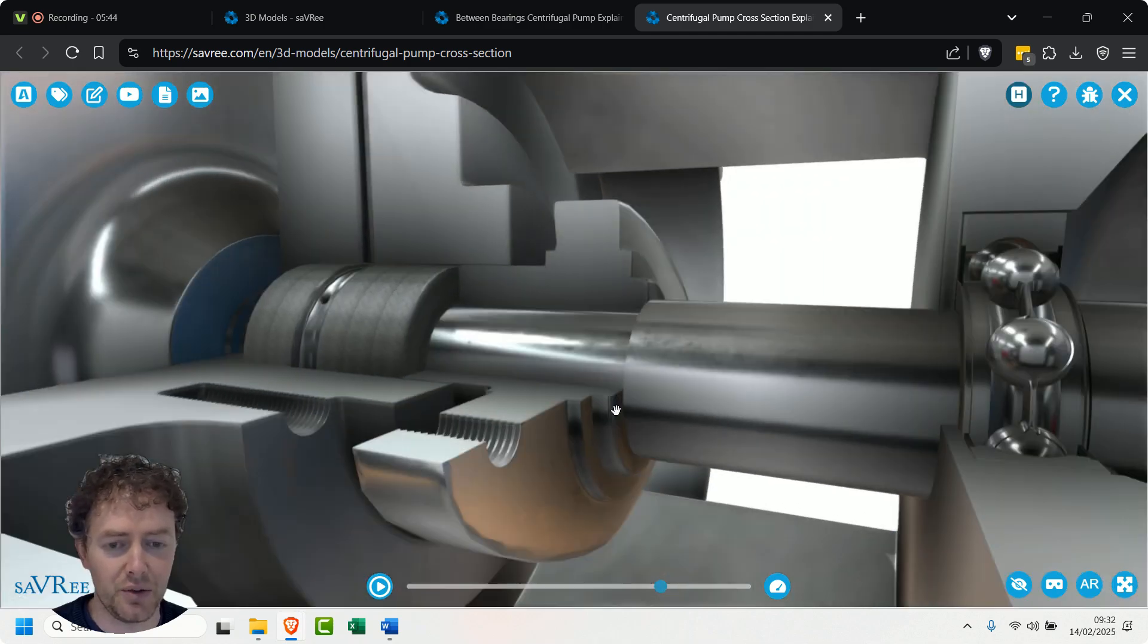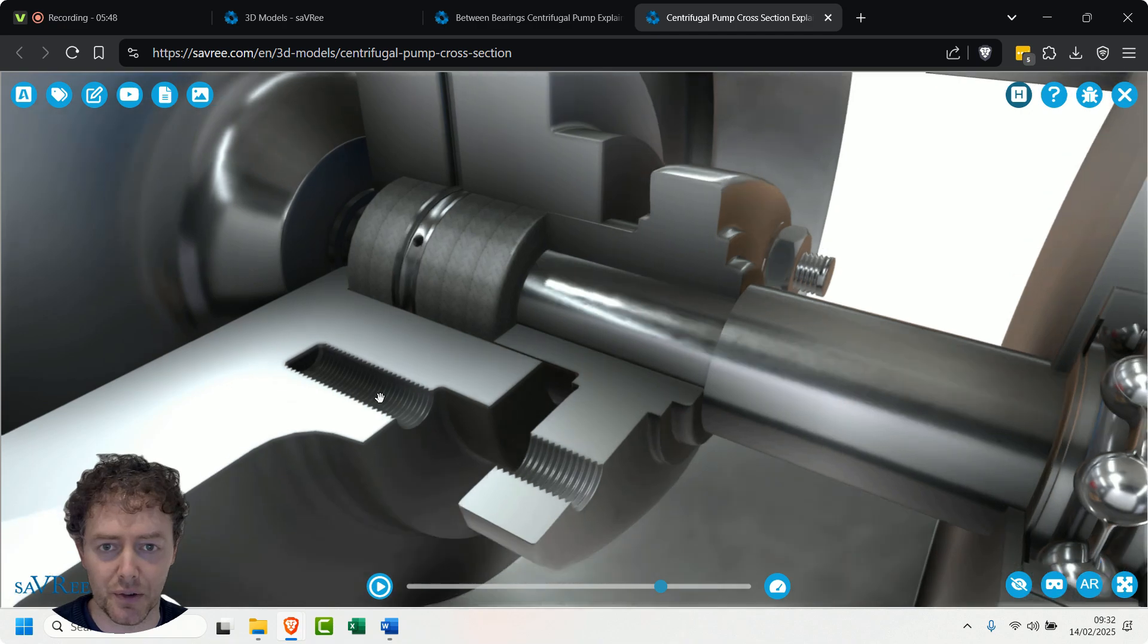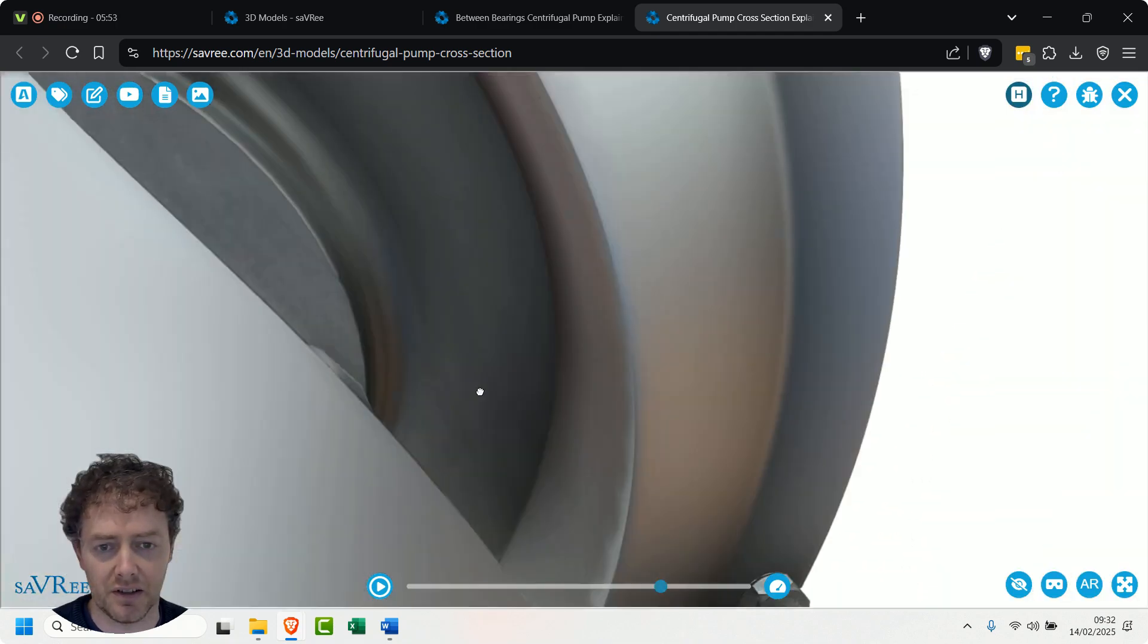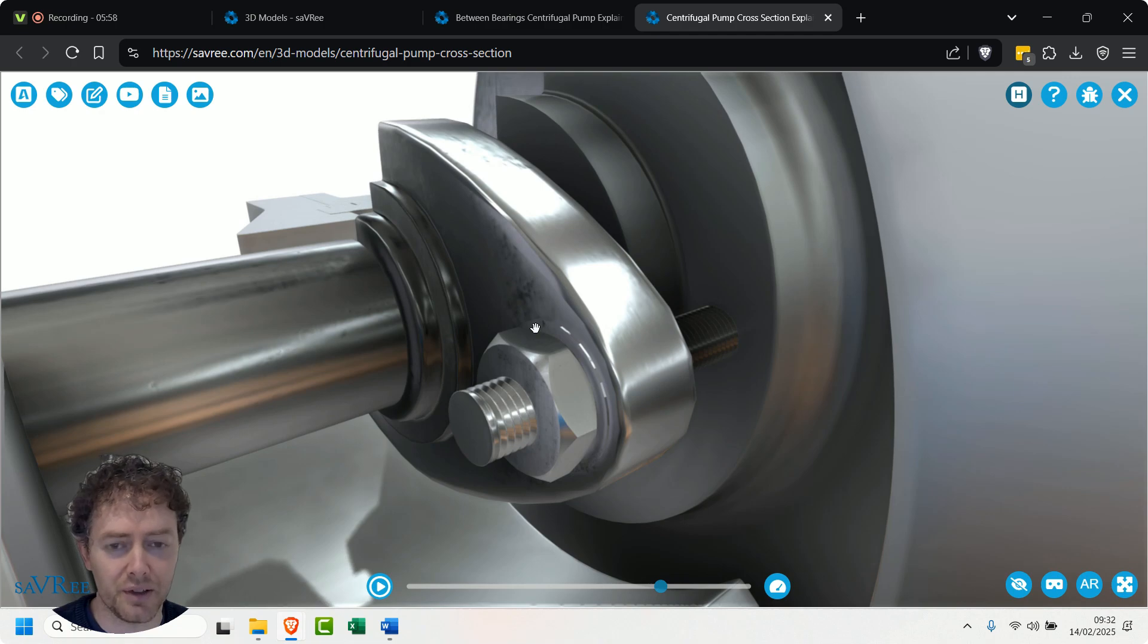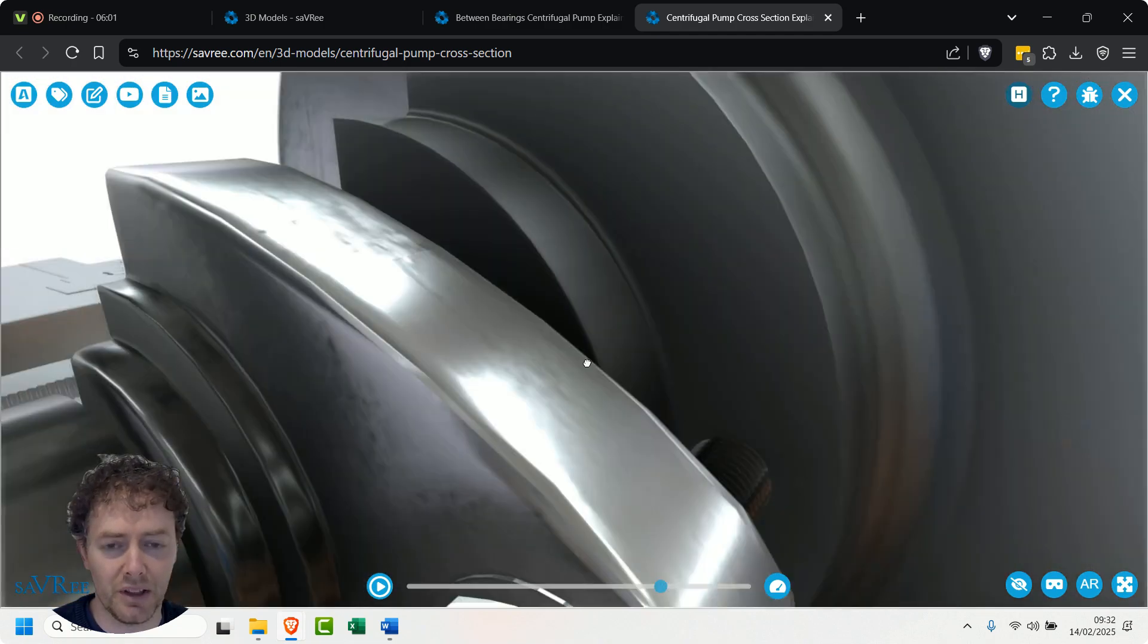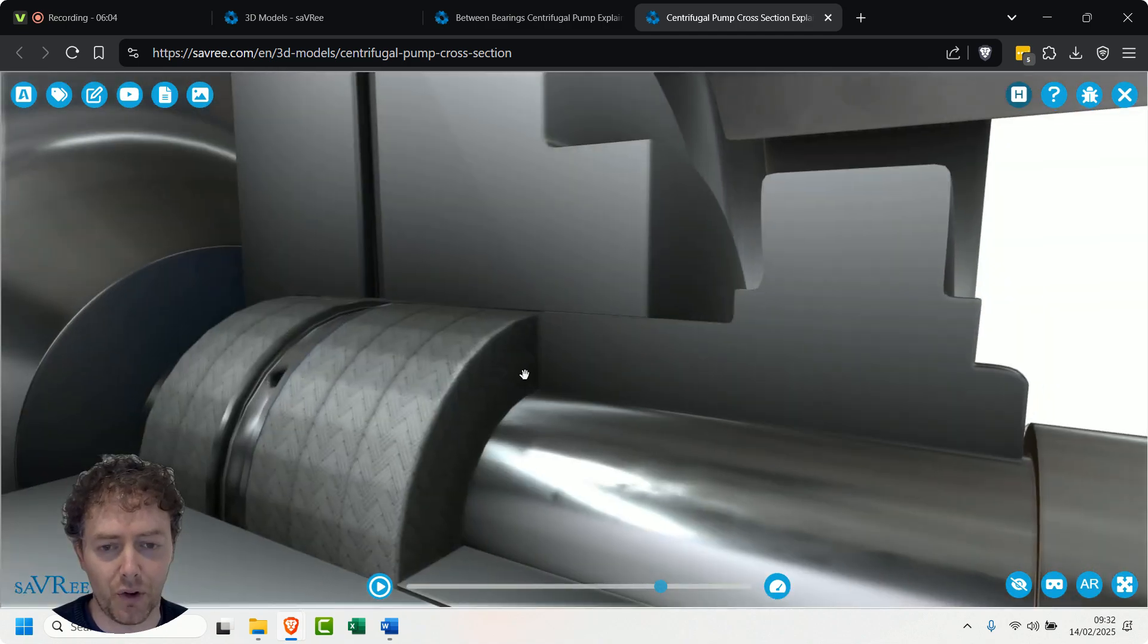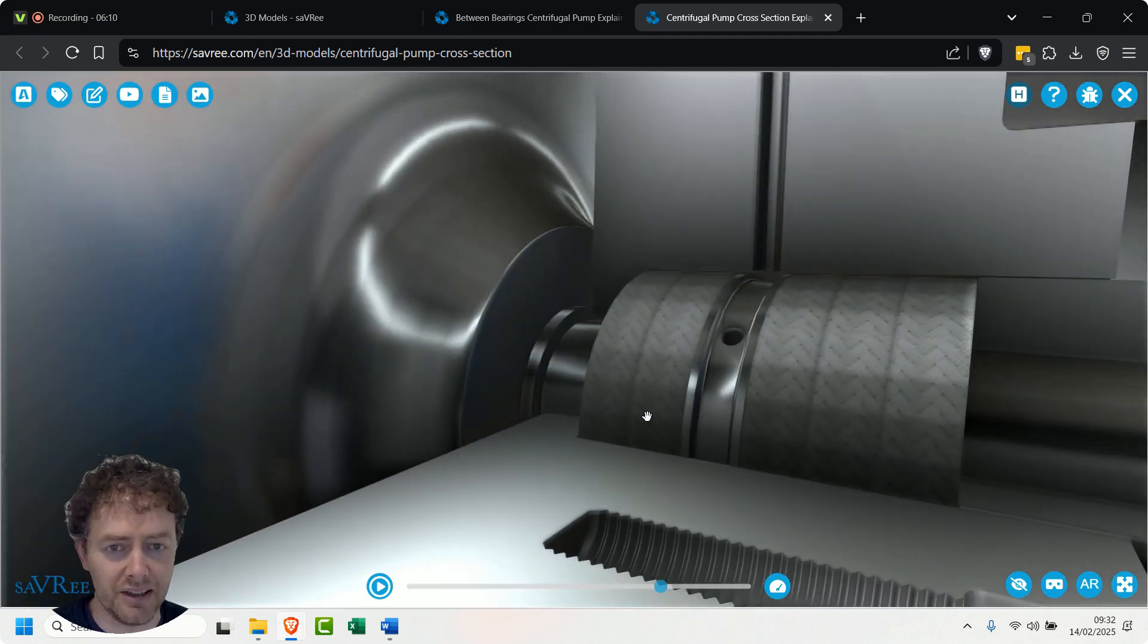This is a gland follower where my mouse is. You can see this screw threads here - let me just see if I can get around the other side here. Okay, so we're tying this gland follower onto the packing material and it's going to squeeze that packing material to such a degree that we don't get any leakage from our volute casing.